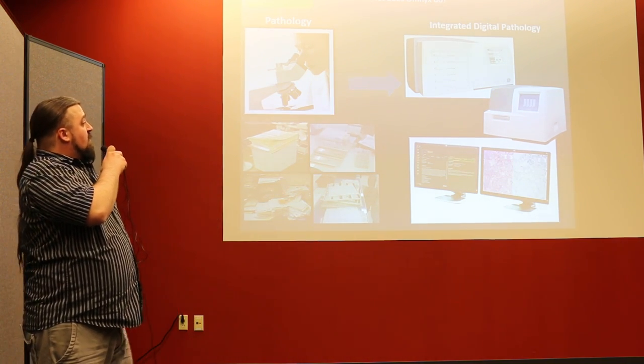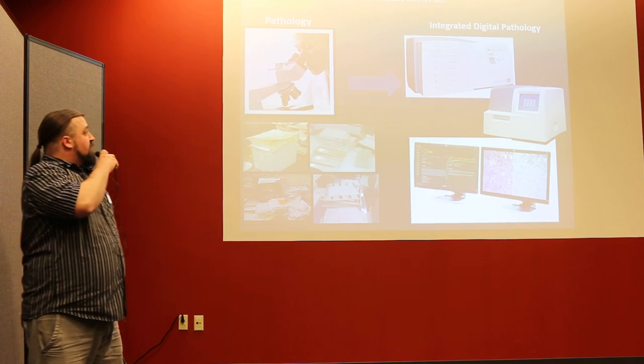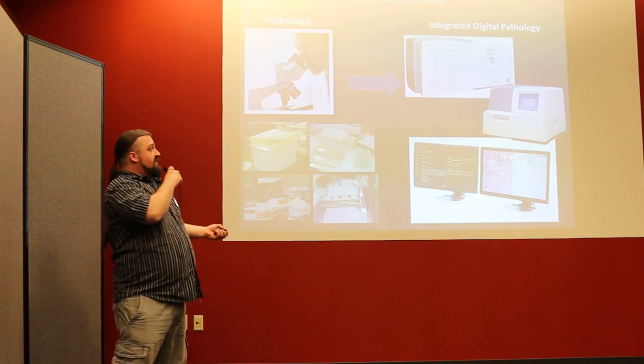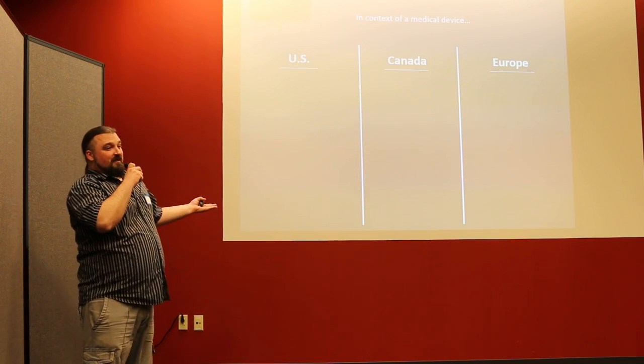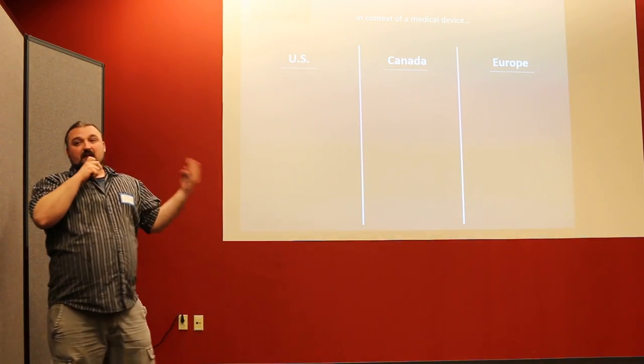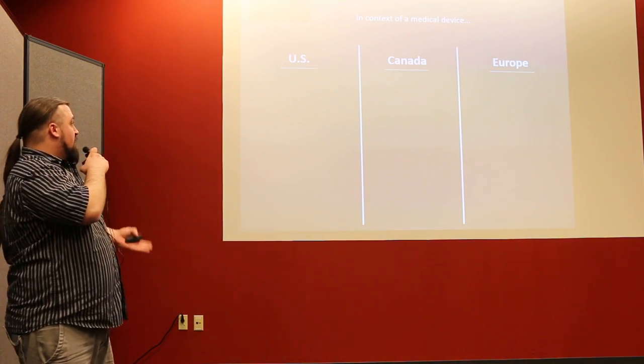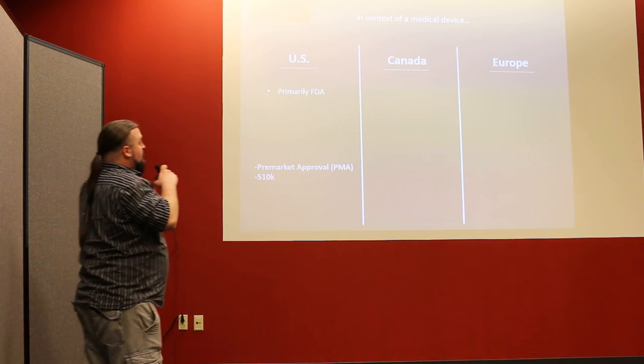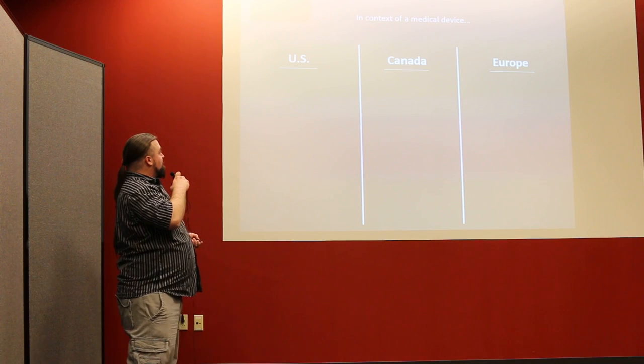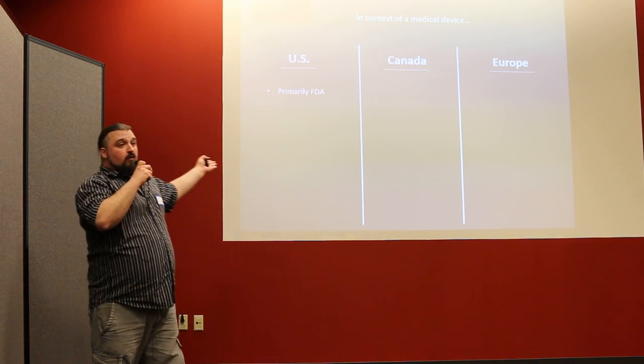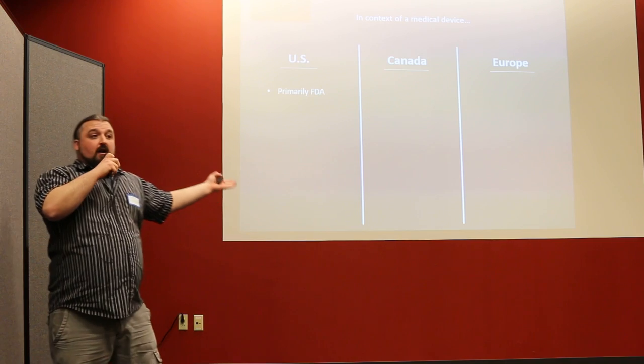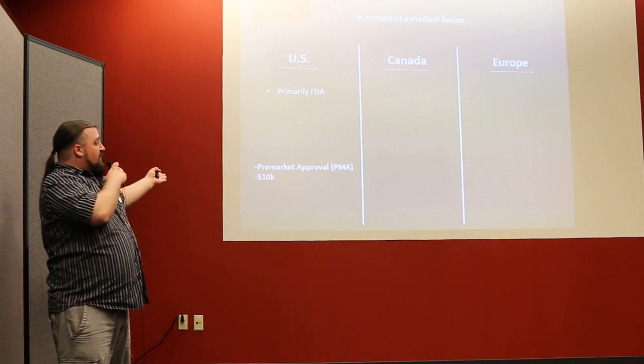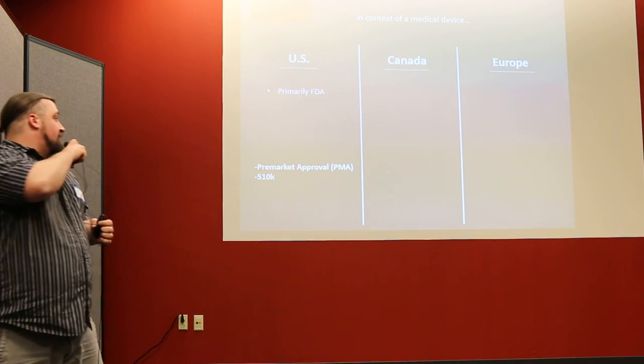So what is involved with building medical devices? One of the very first things you run up against is regulatory bodies. In the context of a medical device, there are some primary players. In the U.S., we're primarily dealing with the FDA, and when you submit for permission to sell, you're really seeking either pre-market approval — a PMA — or a 510K.